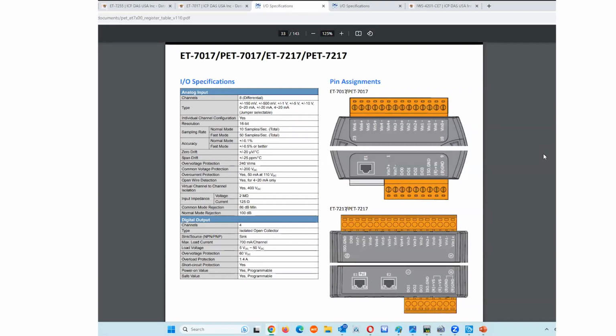Let me just quickly provide a quick schematic and some product details for the ET7017 and similar products. In this case, this module accepts both current and voltage inputs as shown here in the type controls. These are the type of inputs. This module has the ability to sample up to 50 samples per second for analog inputs. We do have faster modules if you need it, but for traditional manufacturing, this is oftentimes fast enough. For the digital outputs, you can certainly tie those in with visual indicators in your robotics applications.